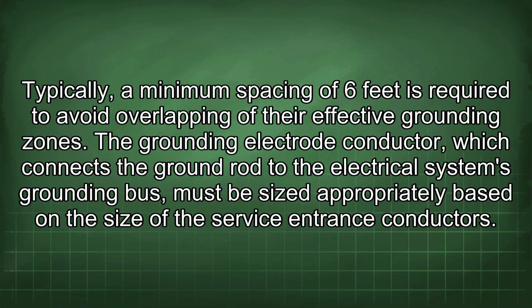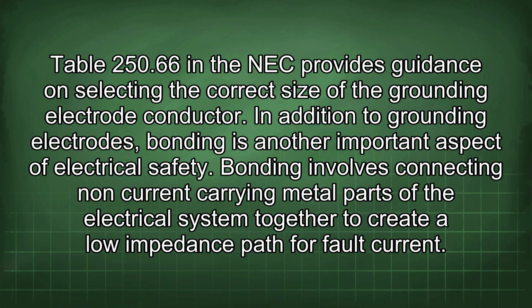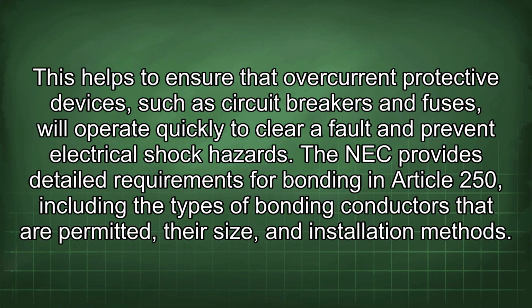The grounding electrode conductor, which connects the ground rod to the electrical system's grounding bus, must be sized appropriately based on the size of the service entrance conductors. Table 250.66 in the NEC provides guidance on selecting the correct size of the grounding electrode conductor. In addition to grounding electrodes, bonding is another important aspect of electrical safety. Bonding involves connecting non-current carrying metal parts of the electrical system together to create a low impedance path for fault current. This helps to ensure that overcurrent protective devices such as circuit breakers and fuses will operate quickly to clear a fault and prevent electrical shock hazards.